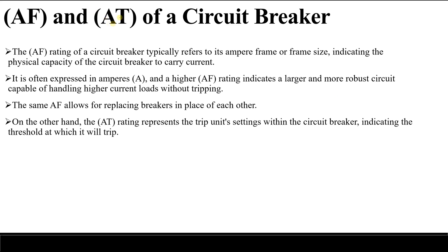On the other hand, AT stands for ampere trip. This represents the trip unit settings. For example, if the ampere trip is 100 amperes, it means the circuit breaker is adjusted at 100 amperes, and at 100 amperes it will trip the circuit. So AF represents the maximum current capacity at which it can be operated, while ampere trip represents the value at which it will trip if the current exceeds it.